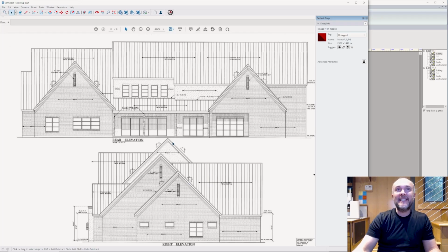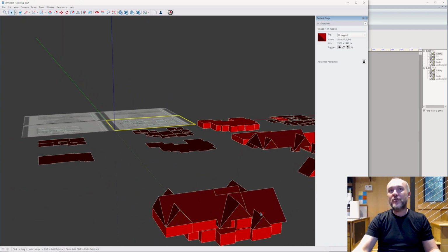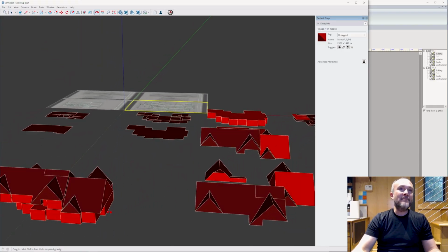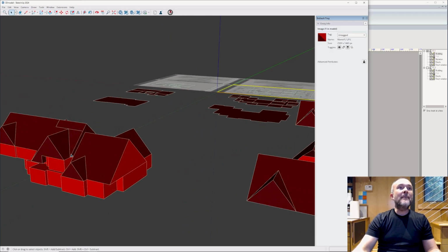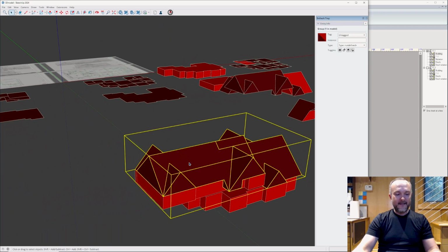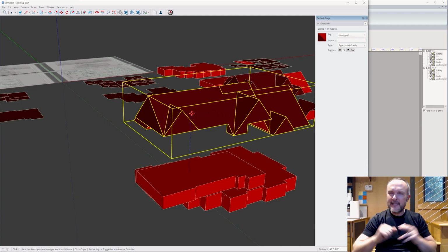So if you're going to encapsulate this space, what I like to always do is build them into the actual 3D model. Here's your first example of why HVAC professionals do not do what I am describing. I'm going to build this entire room here, which is, as you can see, sitting on top of the two floors. So again, if I was going to do a typical HVAC design on this, I would just do those two big blocks. What I'm going to show you today is called a block load. We're not worrying about specific rooms in this plan. But we can then build this room on top of it in 3D.